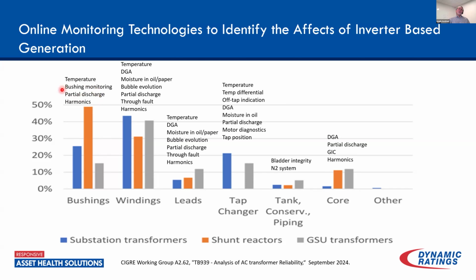Partial discharges, as we talked about earlier, in the presence of harmonics and pressure changes and things like that, we do expect to see an increase in partial discharge activity. And of course, monitoring harmonics, we've talked about. When it comes to the main tank, the windings and so on, it's really not that much different. We're talking temperature. Of course, DGA is pretty much common, whether you're doing key gas or a multi-gas monitor. Putting some type of DGA monitoring on the transformers themselves is almost a guarantee. Most manufacturers or most renewable providers are putting some type of online DGA on those transformers to identify increased gassing, and it's fairly cheap insurance.